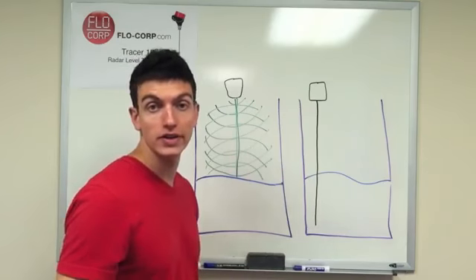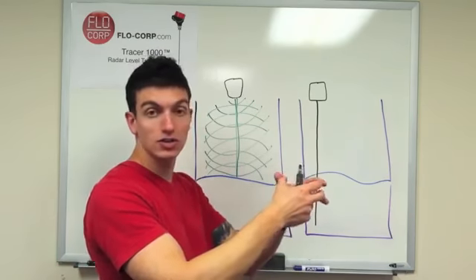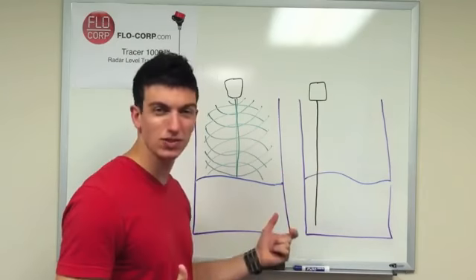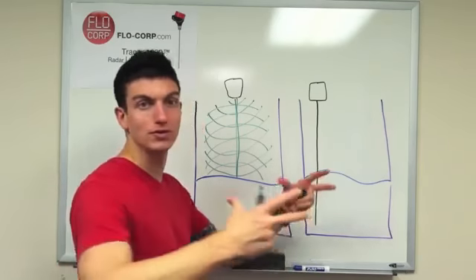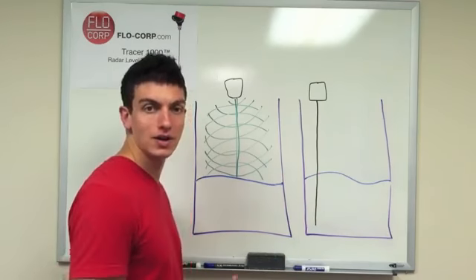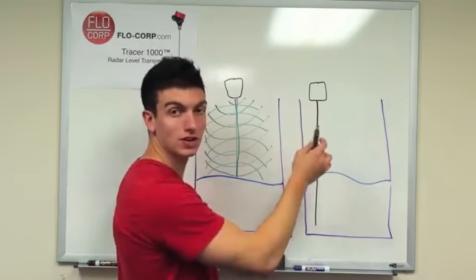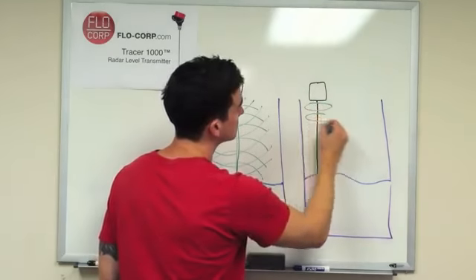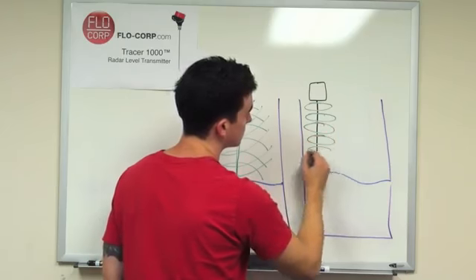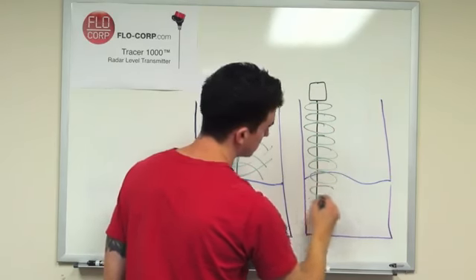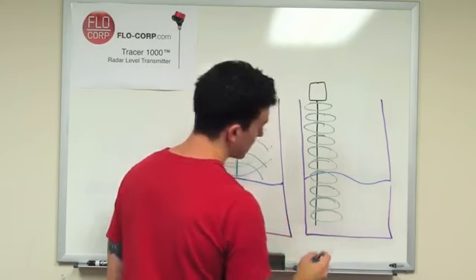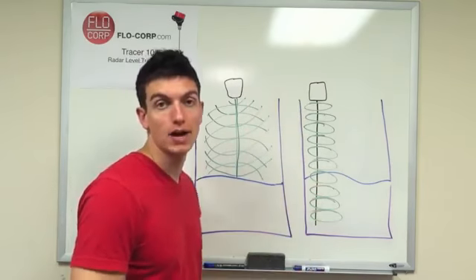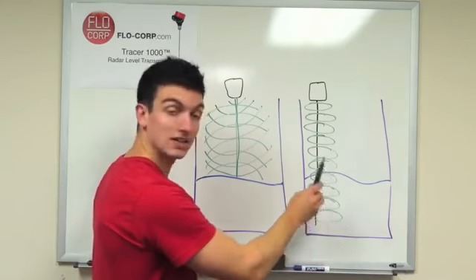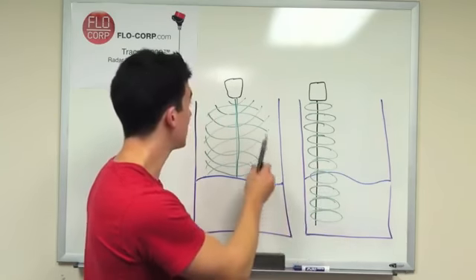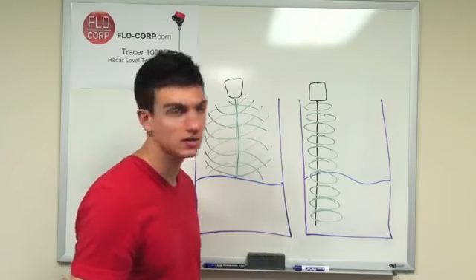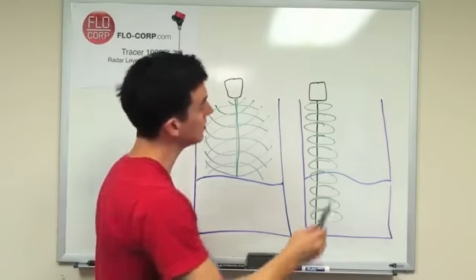Guided wave radar works a little differently. The signal will come out in a circular pattern from the probe, kind of like if you threw a rock in a pond, the ripples go straight out. That's the idea behind how radar measures. So it's going to measure more in a circular pattern here. And it will take that measurement all the way down to the bottom of the probe. Again, this is happening 70 times per second, whereas this is taking one measurement every 2 to 5 seconds. So how the radar works is it's taking all these measurements.